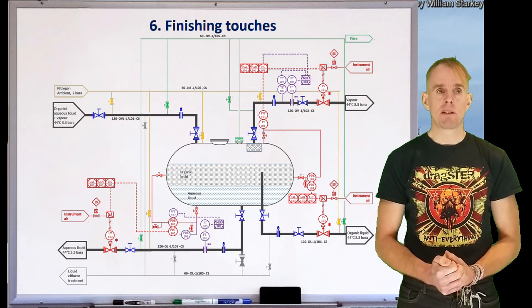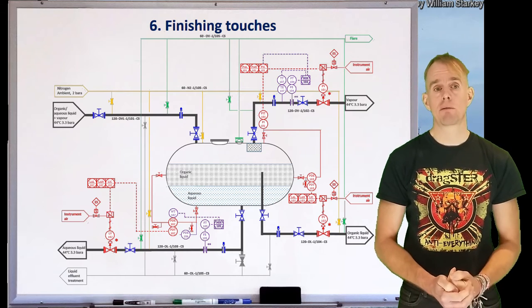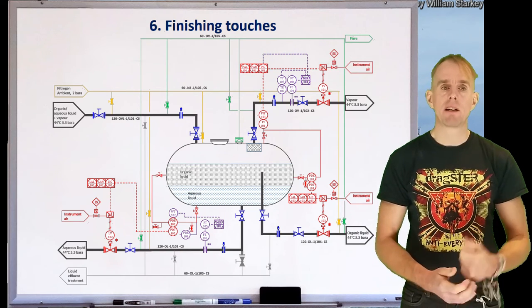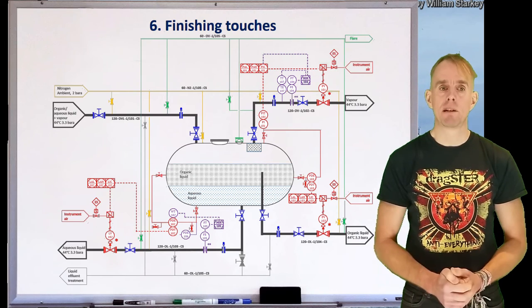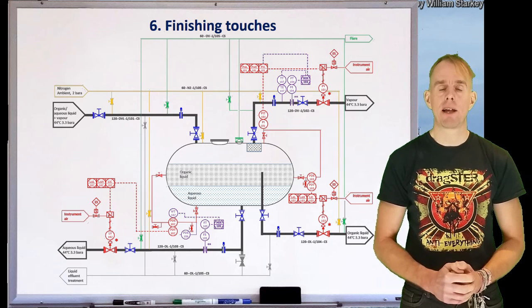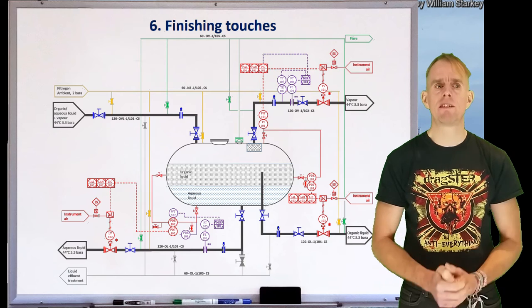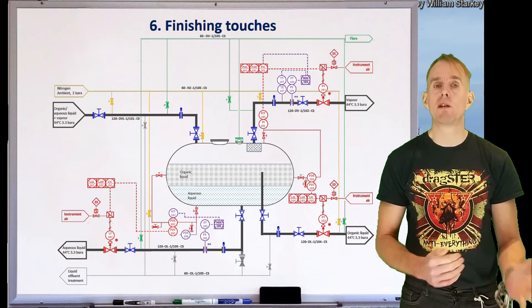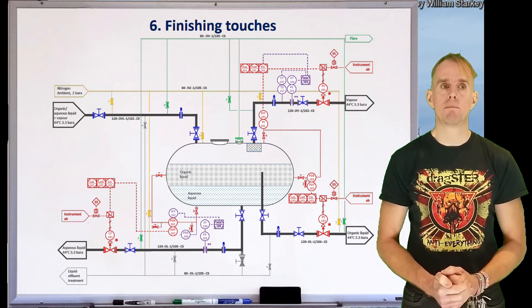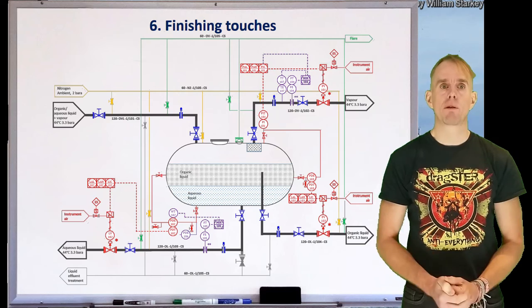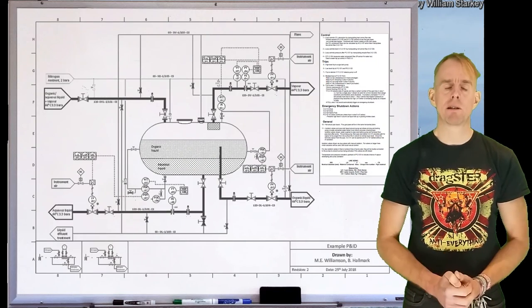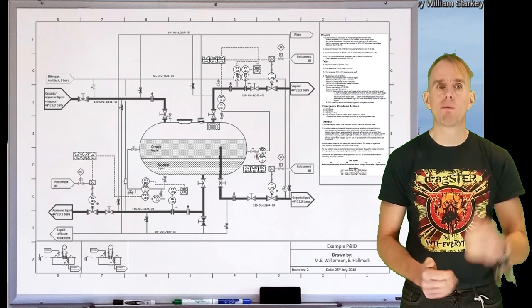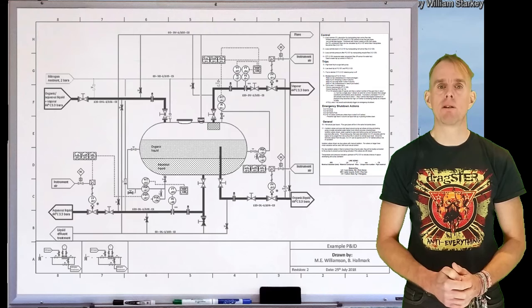We're nearly complete in setting up our P&ID. The finishing touches are to do all your piping calculations, work out pipe diameters, and generate a piping code for each line — including nominal diameter, unique line number, material information, pipe materials of construction, insulation and trace heat requirements, illustrated on every single line code. We've also added more detail onto the entry and exit tags, describing conditions, pressures, and continuation information — where the streams come from and where they go to. Following this six-step process all the way through will result in a completed piping and instrumentation diagram, developed in a systematic and rigorous way that addresses every aspect of the design.